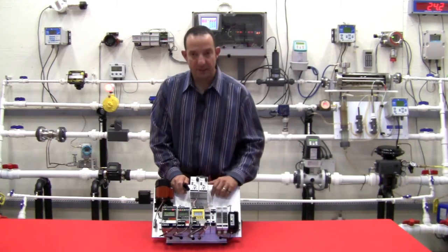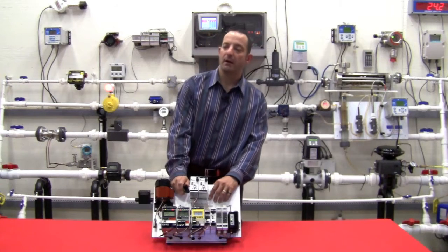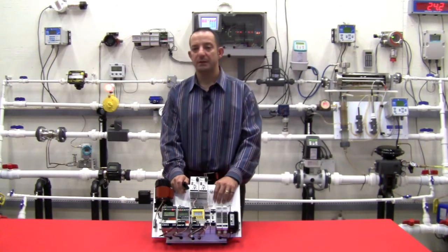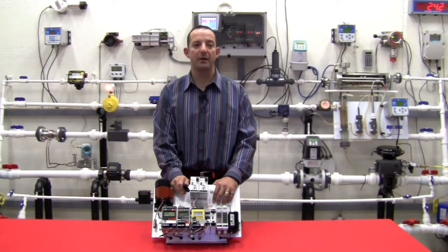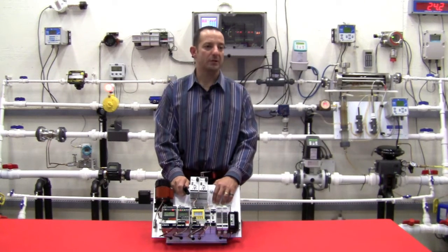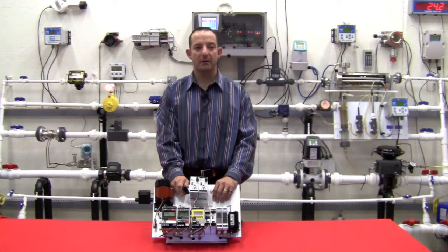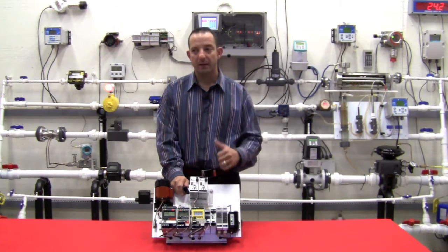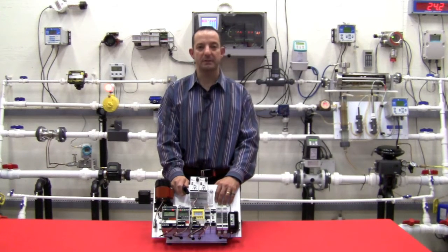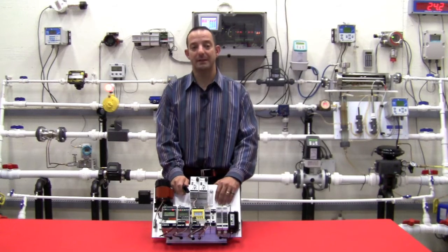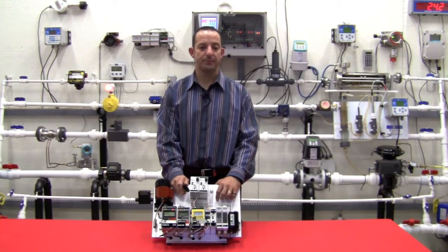Another benefit of using a temperature transmitter is in applications where lightning might be present. The temperature transmitter acts as a glorified fuse in front of the control system, so that a shot of lightning nearby might destroy the $200 or $300 temperature transmitter, not the $1,600 input card to the control system, and possibly take other signals along with it and do much more damage.